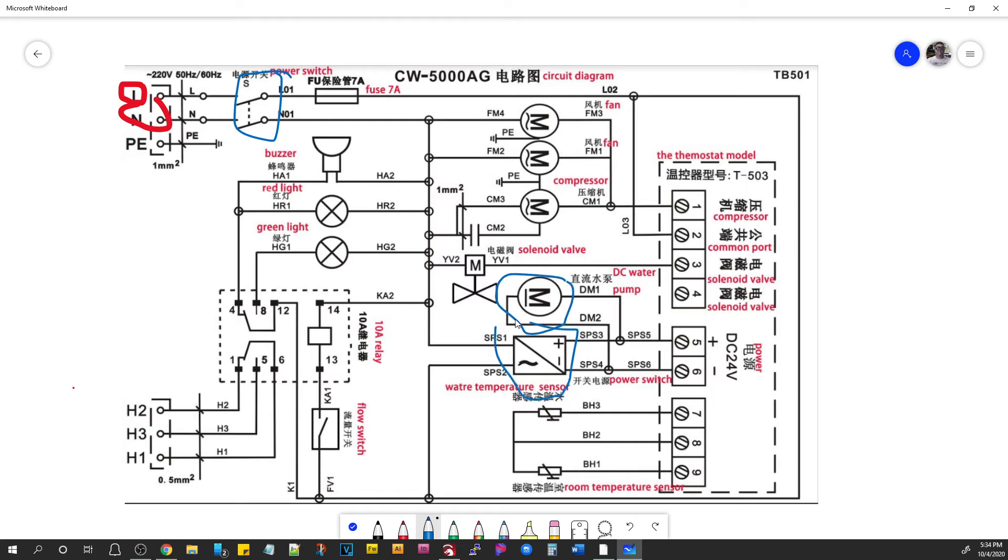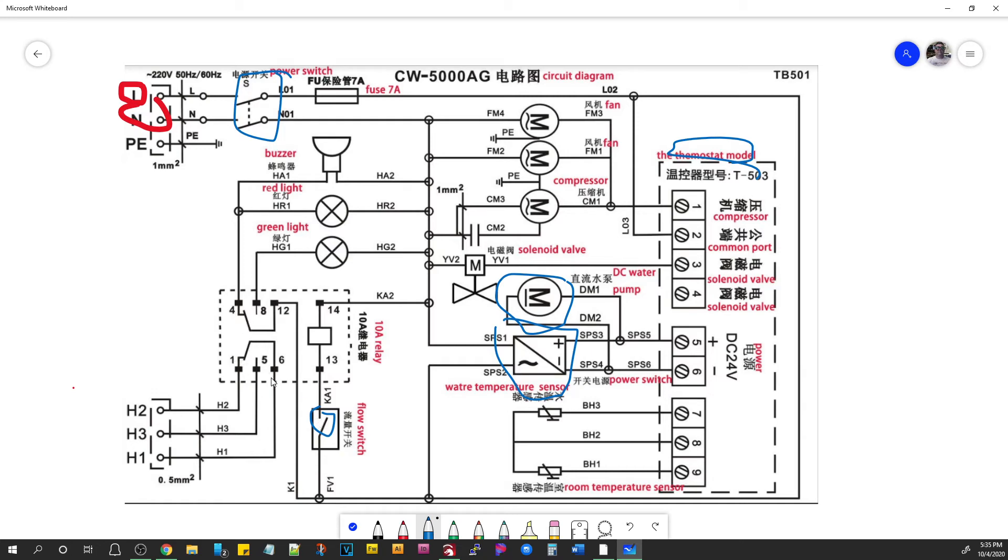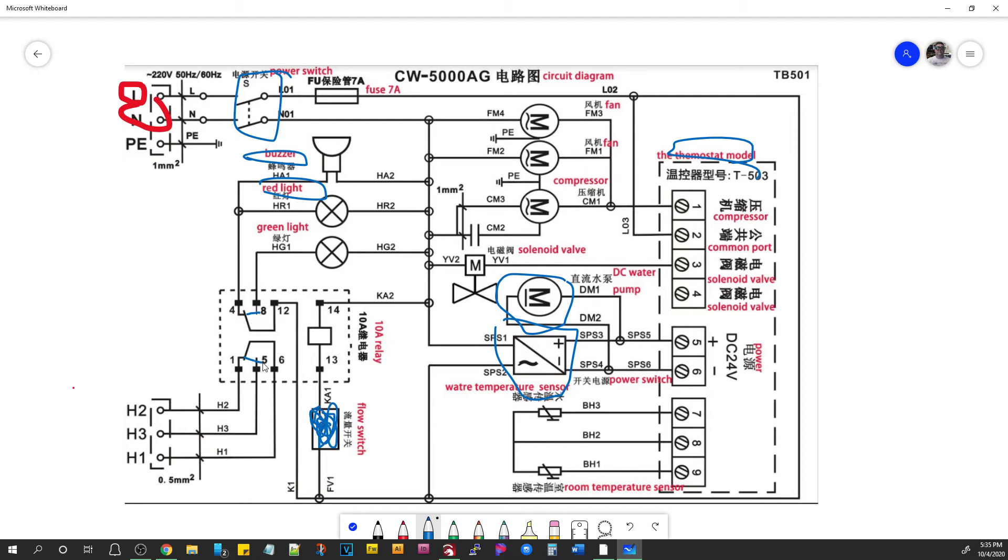This 24 volt power supply and that water pump come on immediately, and so does the thermostat controller. And for just a minute until this flow switch is able to energize when the water gets built up and the flow starts going, this is going to stay closed here, which is giving you an alarm output to the laser indicating a problem and it's activating the red light and the audible buzzer. And as soon as the water starts flowing and this circuit right here is closed, these will switch over and you'll have a good alarm signal coming to the laser and the green light will come on, the red light and the buzzer will go off.